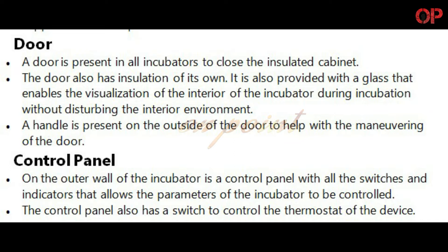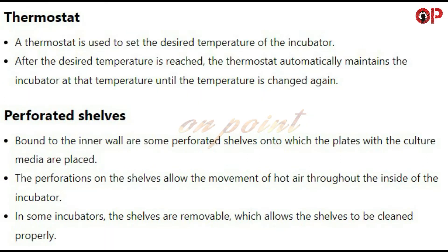Control Panel: On the outer wall of the incubator is a control panel with all the switches and indicators that allow the parameters of the incubator to be controlled. The control panel also has a switch to control the thermostat of the device. Thermostat: A thermostat is used to set the desired temperature of the incubator. After the desired temperature is reached, the thermostat automatically maintains the incubator at that temperature until the temperature is changed again.